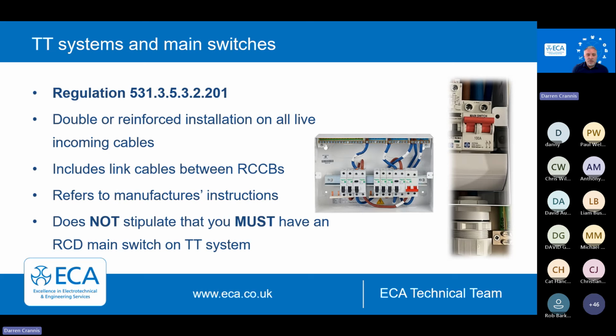There may be times where you just want the 30 milliamp RCBOs on all outgoing ways, and that'll be fine. If you've got distribution circuits in there and you want that 1 second disconnection time, then you probably are now looking at changing that for a time delay coming out of the main switch. So it's just options really for you. But importantly, you don't need one. The requirement is your 0.2 second disconnection or your 1 second disconnection times, but you may need to, depending on how you design your installation.